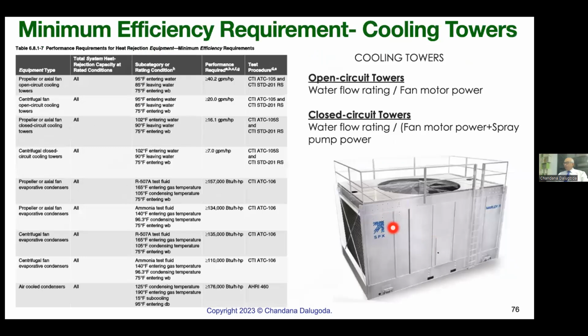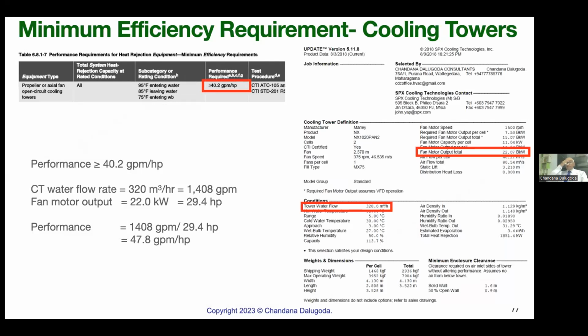Then the cooling towers, there's a value, a minimum energy efficiency value. Let's see what it is. When we select a cooling tower, we have a flow rate. The performance index in 90.1 is 40.2 GPM per horsepower. Now we'll have to find this.